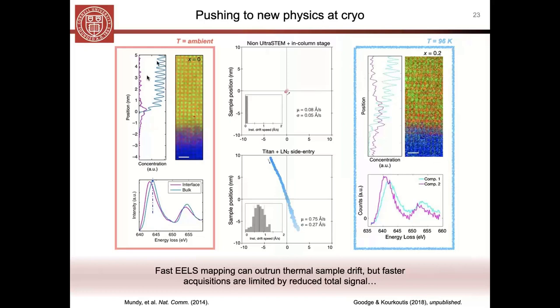This room temperature work was done on a Nion UltraSTEM we have at Cornell with an in-column, fixed cartridge stage. For people familiar with Nion instruments, the sample is deposited directly in the microscope column and completely decoupled from the external environment, which gives you these incredibly low drift rates.